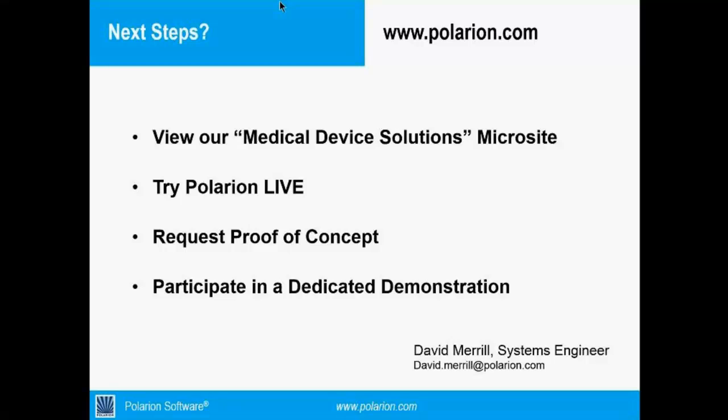What that allows us to do is pull harms into the design control process, so it acts as a driver to the design inputs, so we can start to think about what types of features you might need in your device to mitigate a harm that they're seeing in the field. And that always plays well with your tech file submission and or your 510K submission, because you've identified those risks already, and it's all part of your design control.